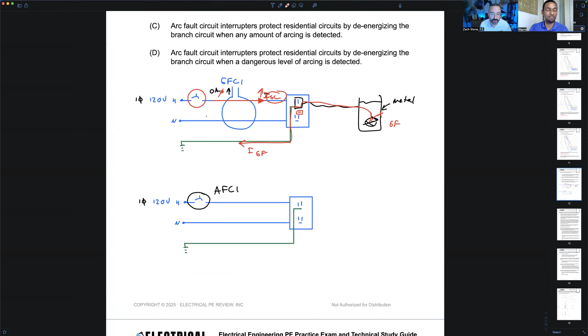Arc fault circuit interrupters, the difference is instead of looking at differential current coming in and going out, they detect arcing current. They detect little arcs. How many times, Wayne, have you plugged something in and you see a little spark? A lot? Yeah, all the time. Or even sometimes when I'm flicking a light switch, I can hear a little crackle, halfway between. Yeah, if you do that, you will probably trip it if you have an arc fault circuit interrupter. But yeah, that crackle is an arc.